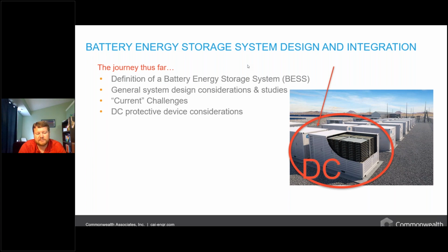What we're seeing in the industry right now is more and more AC coupled systems. Now, for an AC coupled system, making the argument that they're charging directly off renewables can be a bit more challenging and will require metering, but it is possible through control systems to do this. What we find is you have more available inverter technology in the market, and what I'm seeing is the vast majority of inverter manufacturers are focused on AC coupled systems. So you're going to have the latest and greatest equipment. And we're seeing very, very fast-paced changes in technology on these inverters right now.